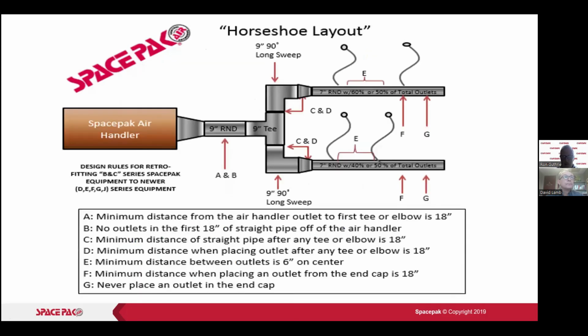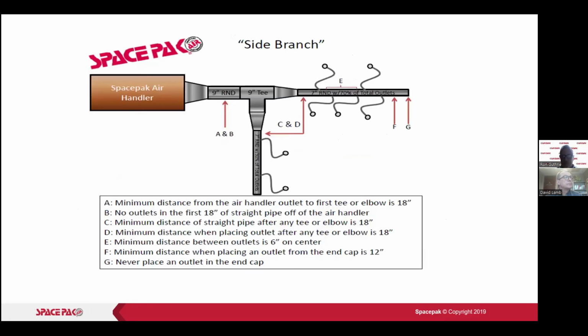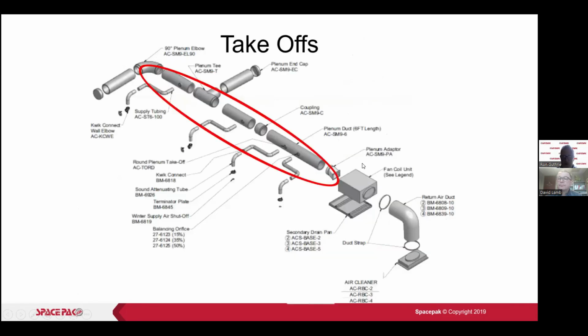On a horseshoe system, we're basically changing out through the T and the elbows, and where we reduce down to the ends of the horseshoe, we're using the 7-inch round. If you can't get that out, you're always better off using 9-inch. Here, same thing. This is the side branch. We're changing all the way through the T to 9-inch and reducing afterwards. So again, this is on the 2430 air handler.